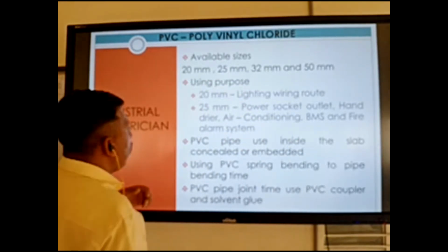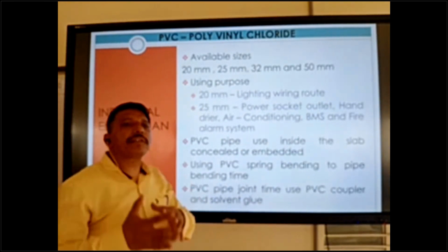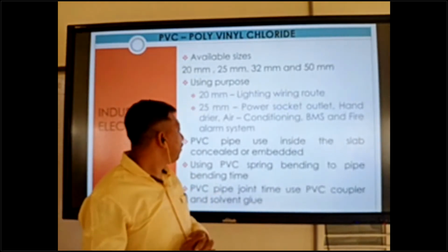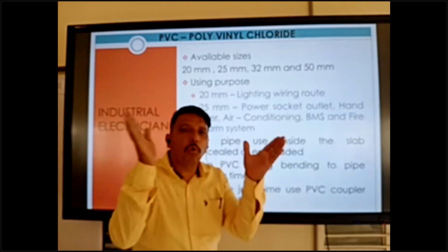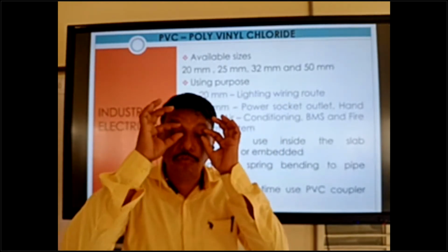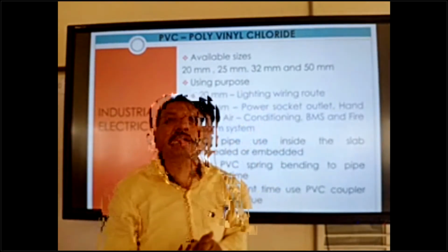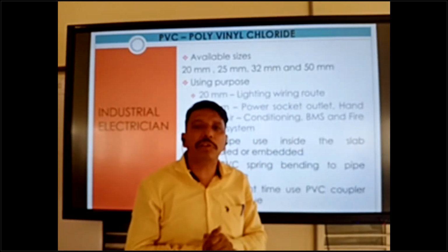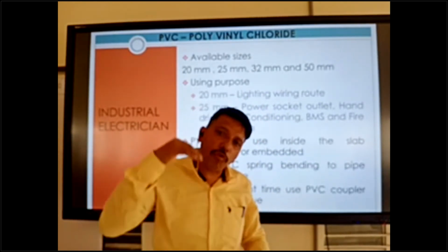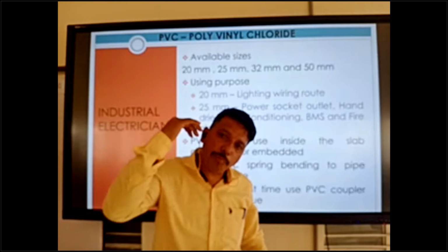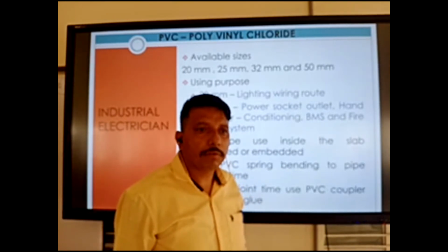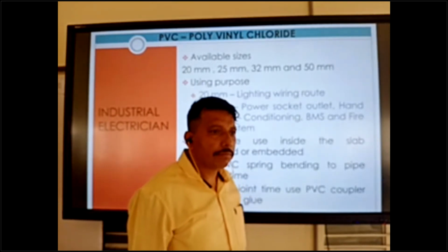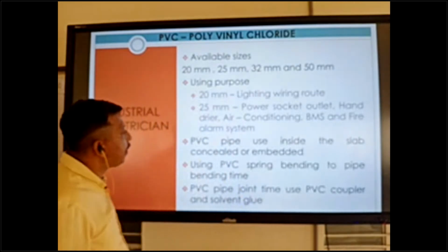If the ceiling is coming there, we can use it in the open also, but if there is no ceiling and you can see it directly, then we cannot use PVC pipe. This is not allowed in Gulf. It should be inside the slab or inside the wall.